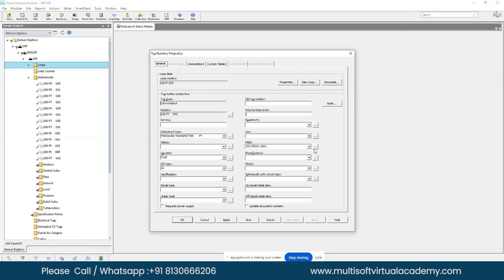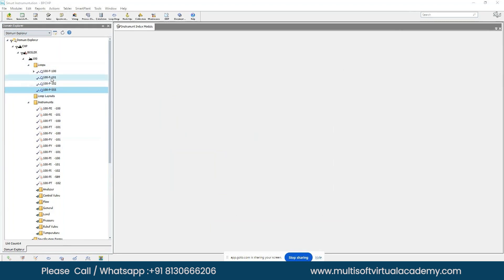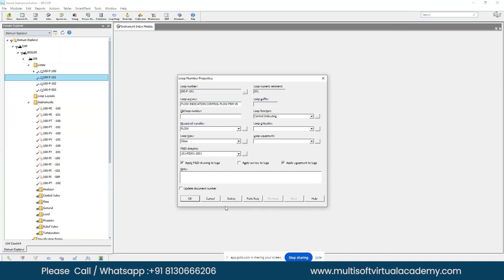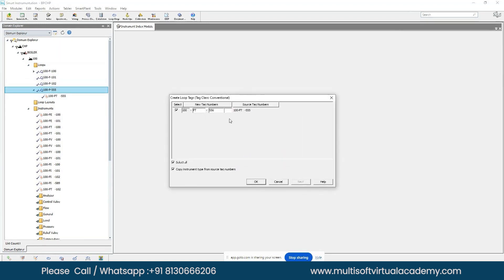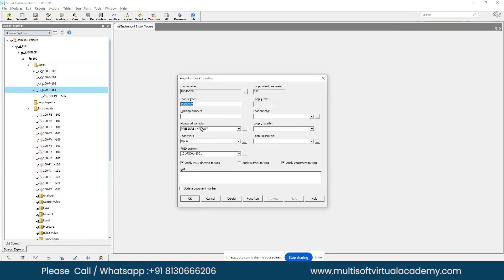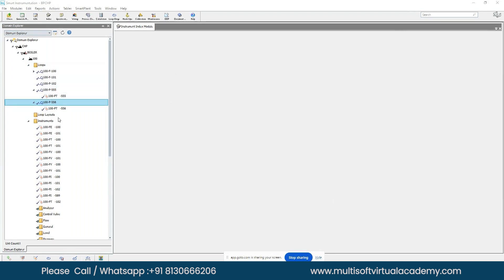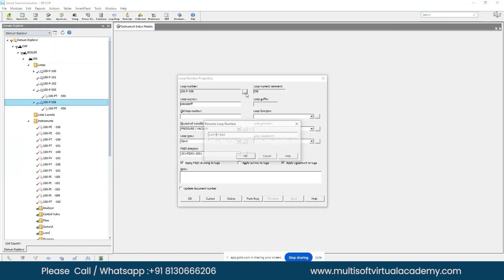The small square boxes you see in the form are supporting tables — they are dropdown menus linked to the supporting table defined on the first day. For loops, right-click on any specific loop and select 'Properties' to update whatever you want. To duplicate a loop, select it and right-click duplicate — the complete loop, including its tag numbers, gets duplicated. To rename a loop, go to properties and use the supporting table — there is no separate rename option.